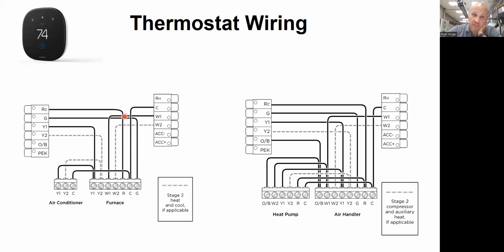So the C wire, that means common, and the R wire, that means red, colored, doesn't have to be, but typically means red, and that's the hot. So R and C provide power to the thermostat, those two wires. The G wire, usually green, that's why it's G, his job is to turn the fan on. The Y wire, usually yellow, his job is to turn the cooling on. And the W wire, usually white, his job is to turn heating on. And if you have two-stage equipment, you might have another Y and another W on there.